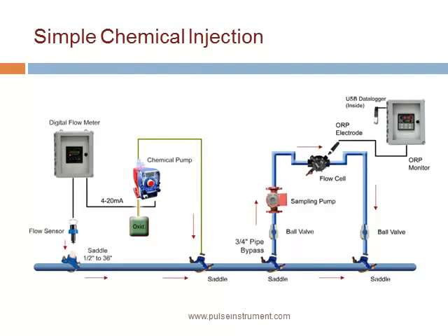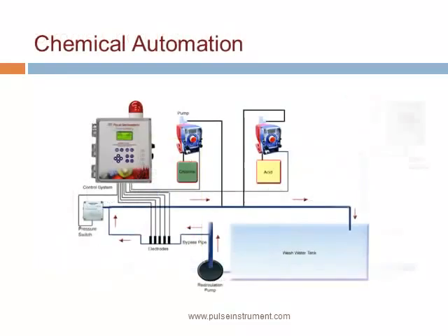A water system may be easily automated for disinfection. A single-pass water line injects chemical on a flow proportional basis with a proportional injection pump. A downstream inline ORP sensor may be used for treatment verification and data recording. In a tank system, an ORP controller with an inline sensor can maintain the ORP level by automatically injecting the oxidizer to maintain the ORP on demand, and adjusts itself to changes in demand from the water source or recycled water.